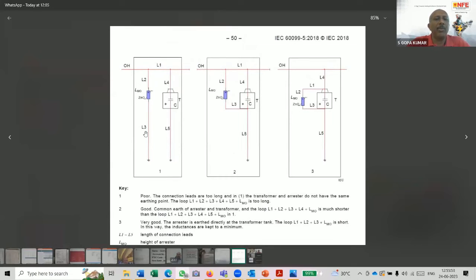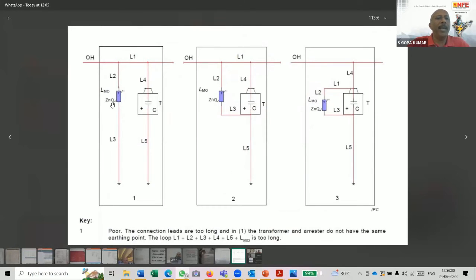Connection 1 is a poor connection because you see the length L3. Let me zoom it again. Between the lightning arrestor, the zinc oxide surge arrestor, and T, the transformer, there is a large loop formed with L2, L3, L5, L4. There is a large loop due to the length of this wire. Your surge arrestor is not efficient in this case. That means if you are connecting your surge arrestor through a separate insulated conductor or a bare conductor insulated from the metallic parts of your installation, and connecting it to a separate earth electrode, technically your surge arrestor or the lightning arrestor, whatever name we call it, will not protect your transformer.